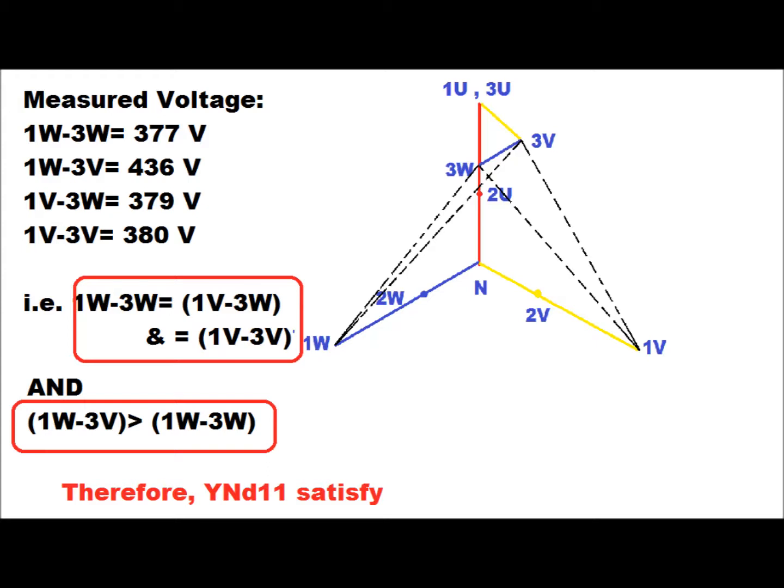We then measure the voltage between 1W-to-3W, 1W-to-3V, 1V-to-3W, and 1V-to-3V as shown in the vector diagram by black dotted lines. The measured voltage between 1W-to-3W comes to 377 V, between 1W-to-3V comes to 436 V, between 1V-to-3W comes to 379 V, and between 1V-to-3V comes to 380 V. We can conclude that 1W-to-3W ≈ 1V-to-3W ≈ 1V-to-3V, and the voltage between 1W-to-3V is greater than 1W-to-3W.